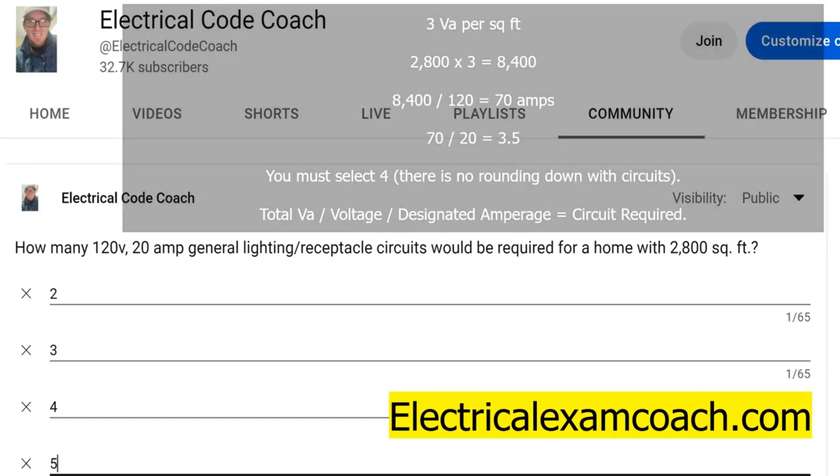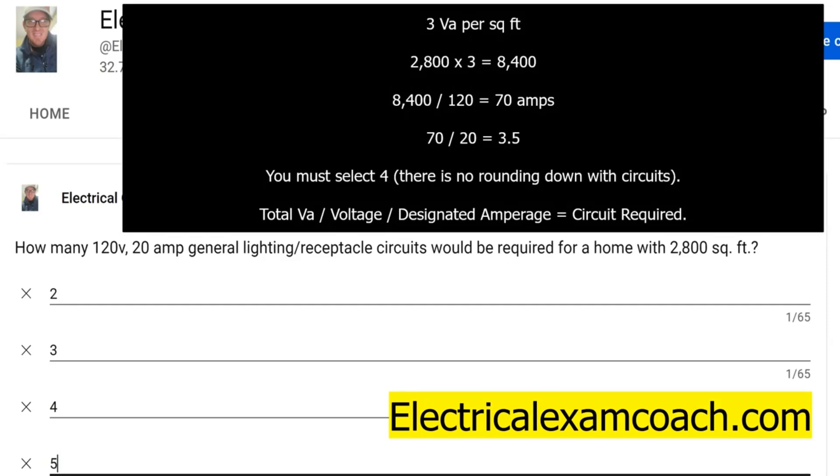Now we know that it's 3 VA's per square foot for this residential home. If you don't know that, you can head over to electricalexamcoach.com and learn all about it from scratch. We take our 2,800 square feet, multiply it by those 3 VA's per square foot, and that's going to equal 8,400 VA's.